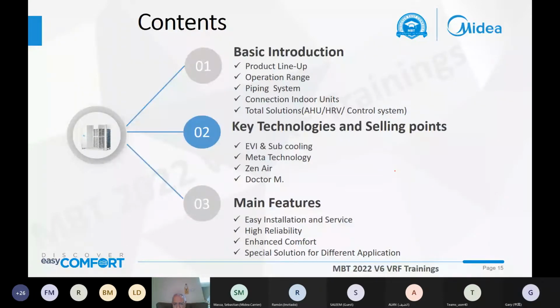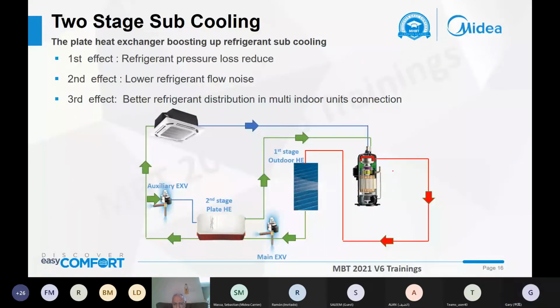Okay, the next part is some key technology and selling points. The first is subcooling. What is subcooling? It means you have one more heat exchange. For the V6, unlike the older generation VRF or other VRFs, which normally have only one stage of heat exchange, we have a second stage. What are the benefits? The first is that we can reduce the refrigerant pressure loss as the refrigerant goes through to the indoor side.